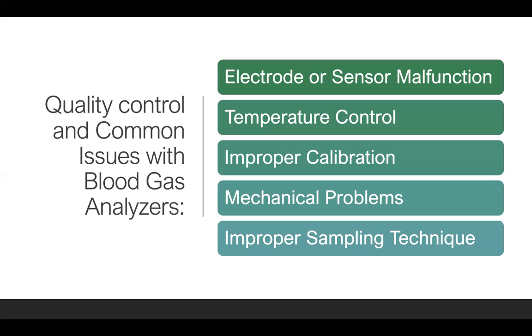We could have improper machine calibration, which could cause inaccurate results. Mechanical problems, such as leaks in the pump, allow our samples to become contaminated. And improper sampling techniques that we talked about a little bit earlier. These include failing to anaerobically collect arterial specimens, improper storage, excessive or no anticoagulant, and bubbles in the specimen, which can all cause inaccurate results.